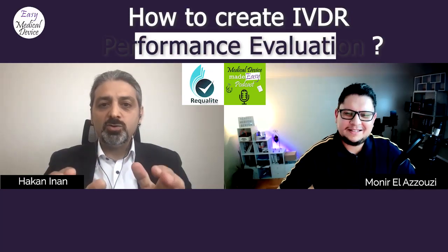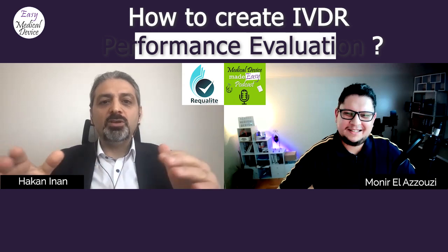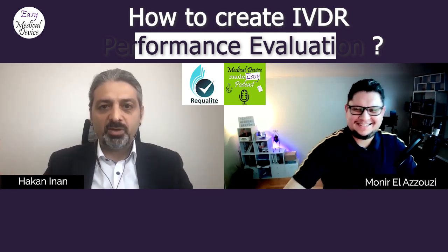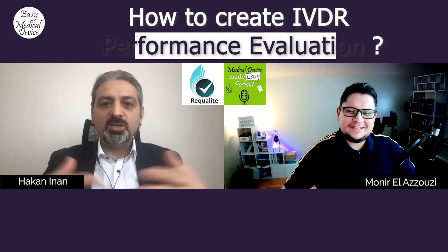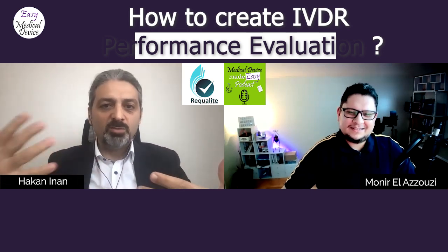And then the 3 reports that I have mentioned: scientific validity, analytical performance, clinical performance. All these things come together and go into the performance evaluation report. But specifically, the regulation also mentions the literature search report in Annex 13. So that means we have to have 5 reports and 1 plan that go into performance evaluation. Of course, we don't talk about the post-market part, because we also have PMPF. So you know that there is an interplay between performance evaluation and post-market performance follow-up.